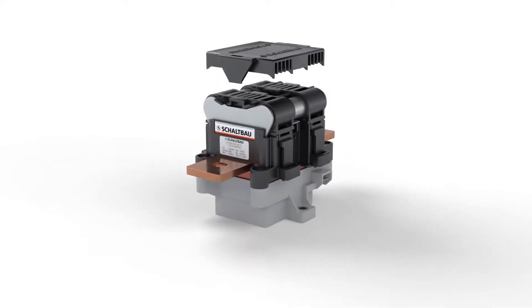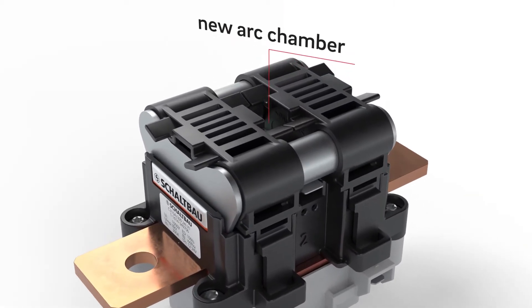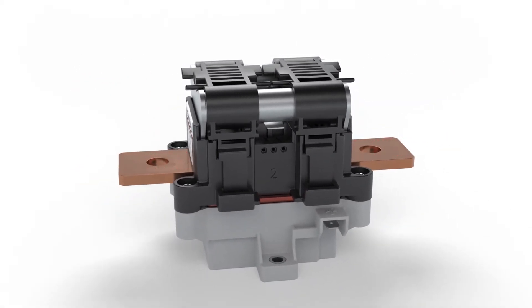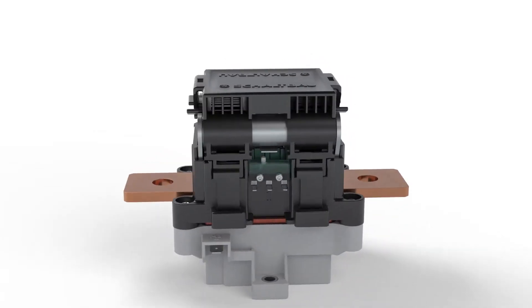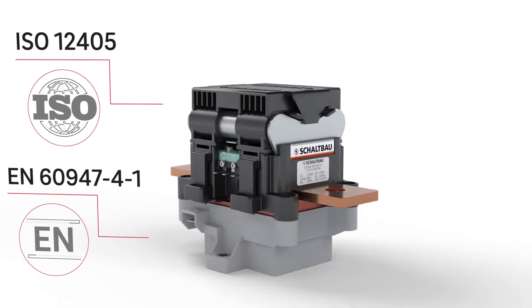With a newly developed highly efficient arc chamber, the switching medium is air. This eliminates any risk of gas loss. Single pole and bi-directional, with double break contacts, high thermal current, extremely good breaking capacity, as well as high short time withstand current to certified safety standards.